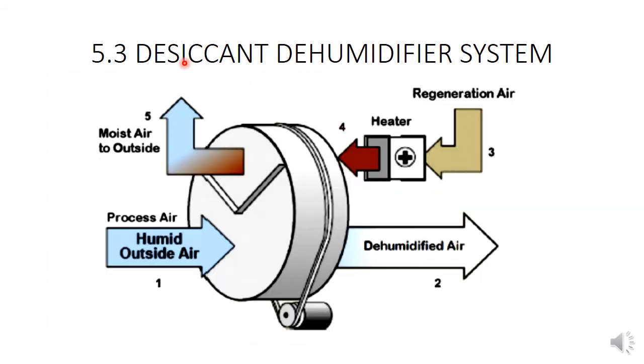Alright, next we have the desiccant dehumidifier system. Basically this is a desiccant wheel. So the humid outside air will go into this desiccant dehumidifier system, and it will pass through the desiccant in this desiccant wheel, and as it passes through the desiccant, the humidity in the air will be absorbed by the desiccant, and there we have dehumidified air.